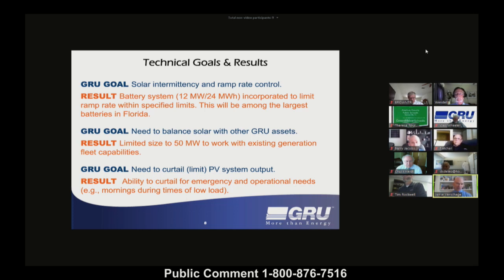Burns & McDonnell took into account GRU's existing electrical generation, modeling units tripping offline and GRU suddenly losing a transmission tie under many different combinations. The study concluded that GRU can add solar, but beyond about 50 megawatts of additional solar, GRU would probably need to add some quick-start generation to back up the intermittent solar energy. So the ITN requested proposals for between 40 and 50 megawatts.